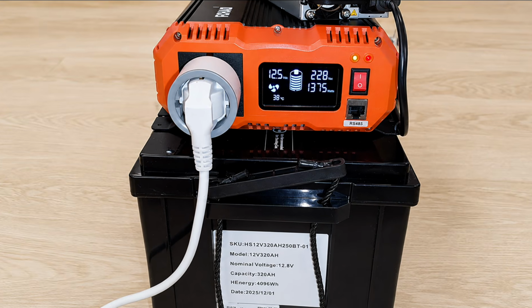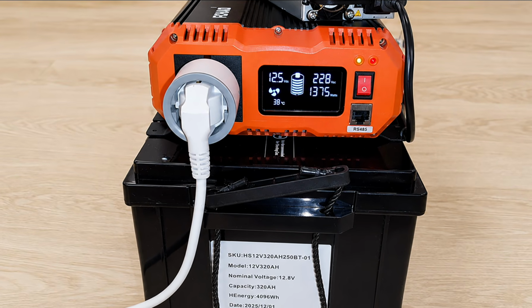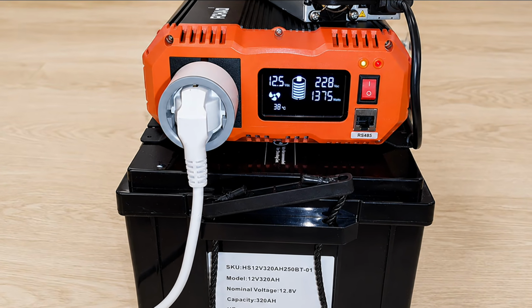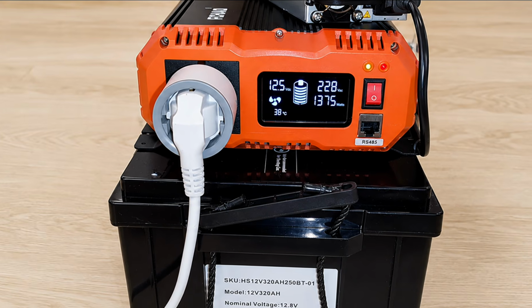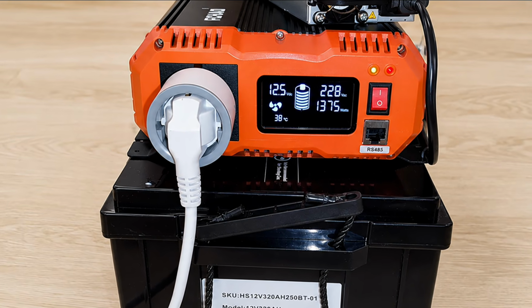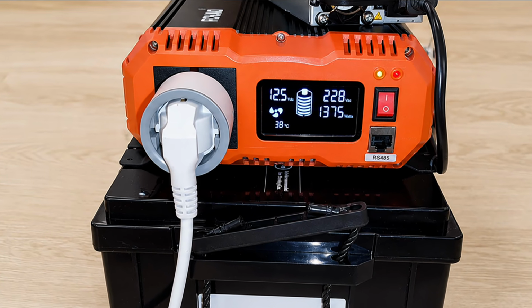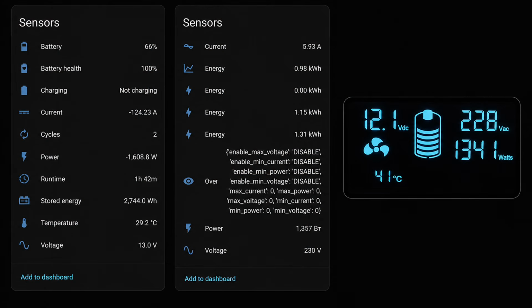That is, at the output we will get the energy delivered by the battery through the inverter, converted, but taking the losses into account, it will be about 20% lower than the internal energy, what the battery actually delivered. The first intermediate check, according to the socket readings, the battery has already delivered 1150 watt-hours of energy, which in terms of pure internal battery energy, is about 1360 watt-hours. The charge level is 66%.